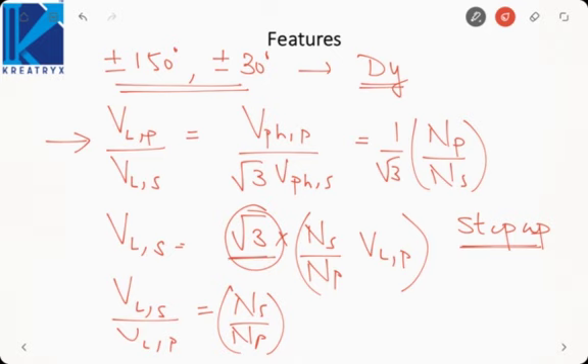Okay. But if we keep the voltage same, then the number of turns would be lesser. So here for the same number of turns we are getting a higher voltage. So to keep the voltage same, the number of turns required will be lesser. Okay. So for the same voltage rating, delta star type of transformer requires lesser number of turns as compared to delta delta or the star star type of transformer.